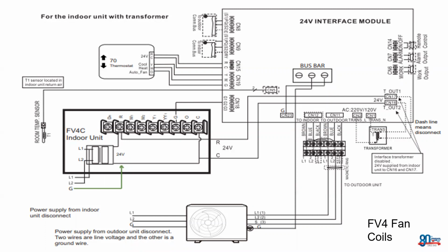Okay, so in an overview, we're looking at a ductless outdoor unit that's powering up L1, L2, and providing a signal to the interface module. We have our 24-volt power, which is supplied from our FV4 printed circuit board from the transformer inside of here. So we're removing the transformer that comes with the interface. We have our 5-wire third-party thermostat set up as a 1 heat, 1 cool option, Y1 being the call for cooling, W1 being the call for heat. And then finally, we have our return air sensor that's going to be relocated to the return air boot of this furnace or this air handler.